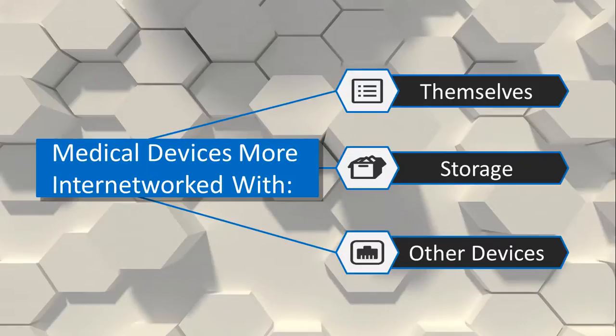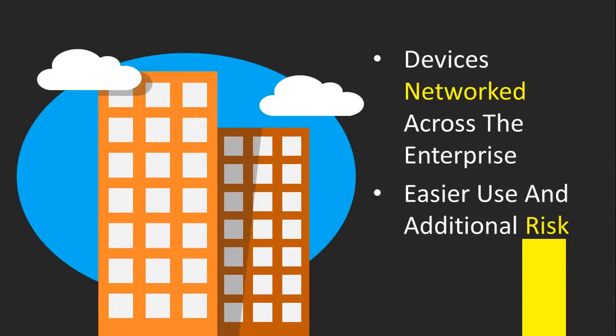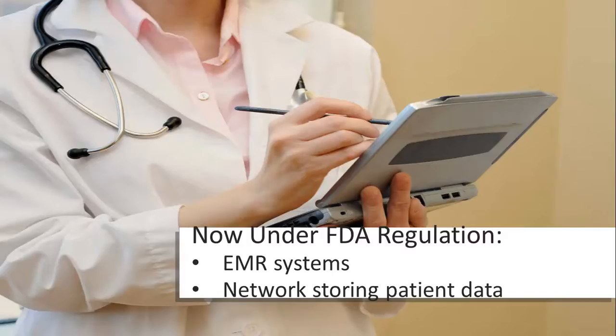Right. This is occurring because practitioners want immediate access to data captured by these systems to improve patient care. Unfortunately, with that immediate access, and where the data is being collected, transferred and stored, there are some risks being incurred. So basically what they're saying is that if you have some type of diagnostic equipment that's now linked to your EMR system, and you're storing some of these images or maybe even just pulling them up on a monitor in a different room, then in essence the EMR system has become a medical device which the FDA is regulating. That's correct. It's not only EMR, but the network that it travels on and where the data being collected is stored.